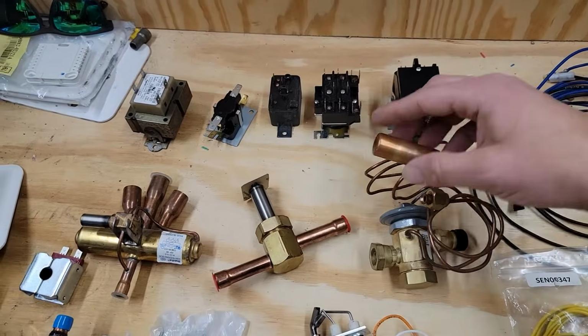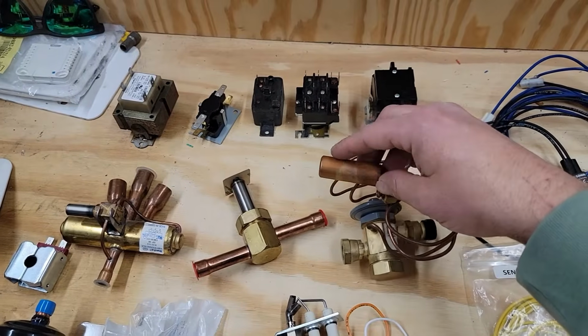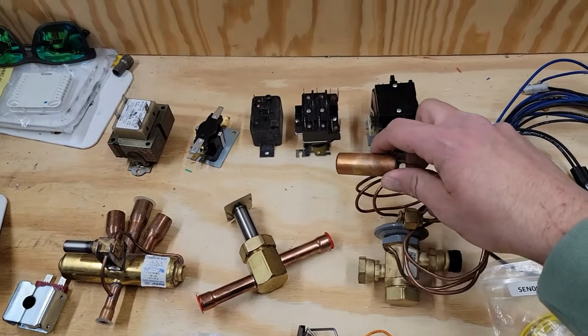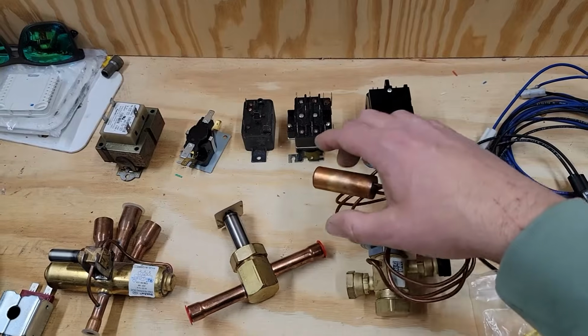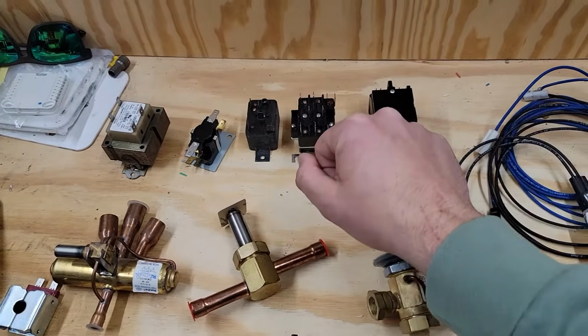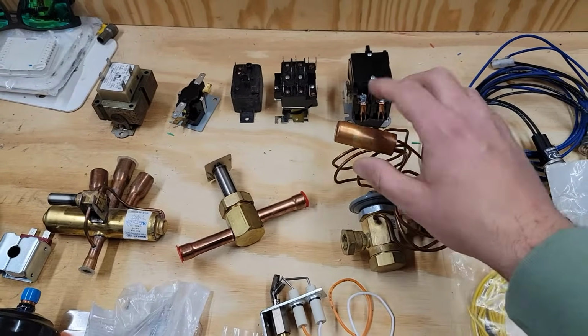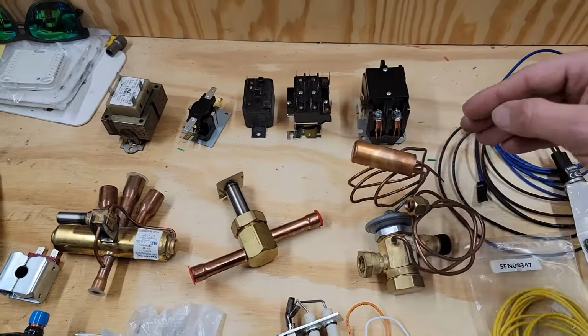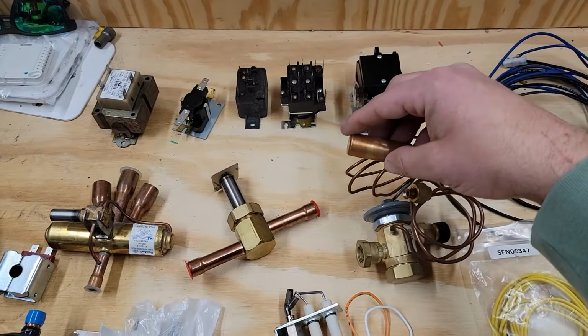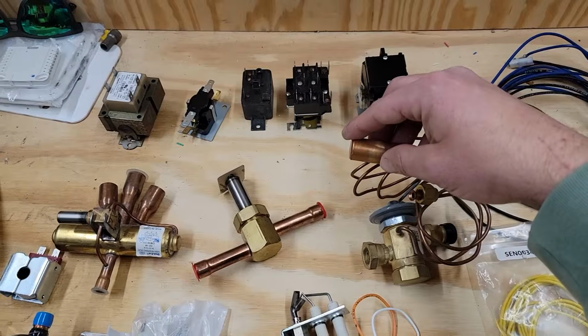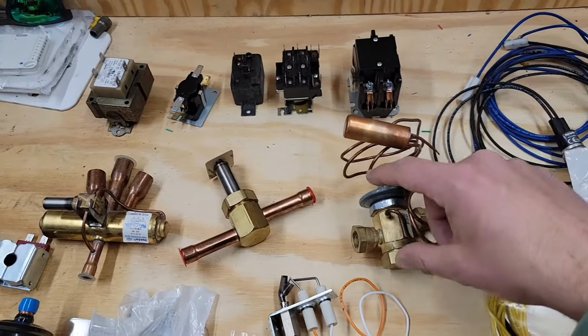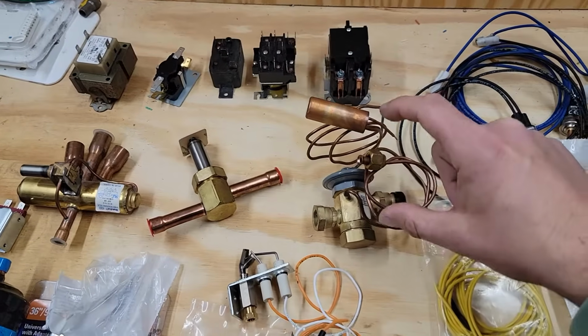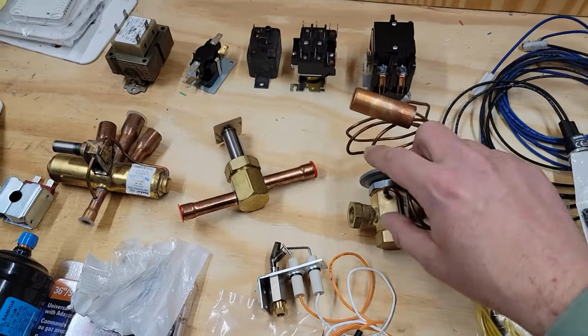And anytime you take this bulb off of the line to where the temperature of the refrigerant is no longer affecting it, if you put your hand on it, it's going to warm it up and it should open this valve. So when this stays on the line, refrigerant's flowing through, it's monitoring that temperature, and the colder this gets, the more this valve will close down. So this is a thermostatic expansion valve.